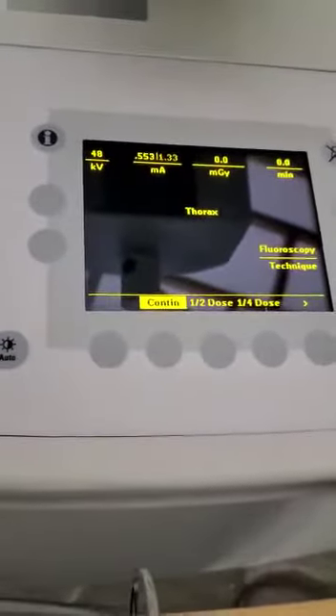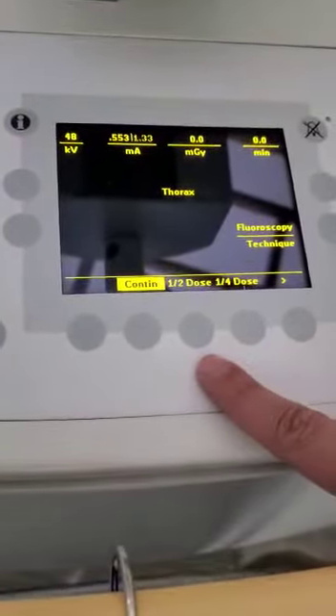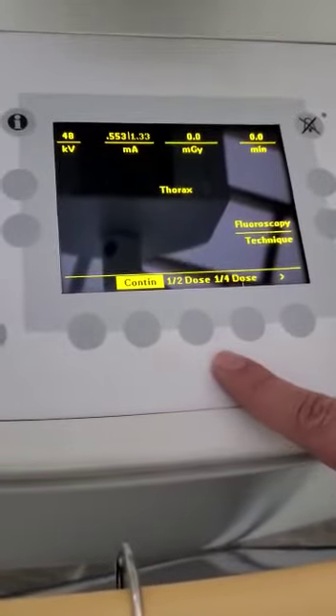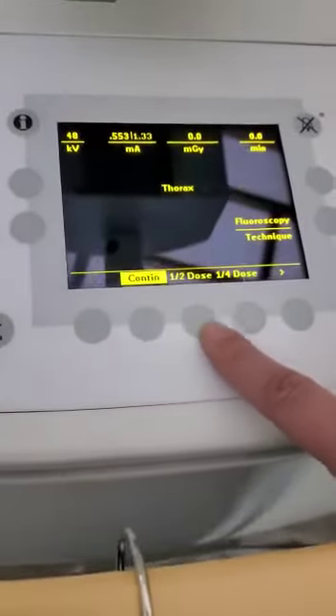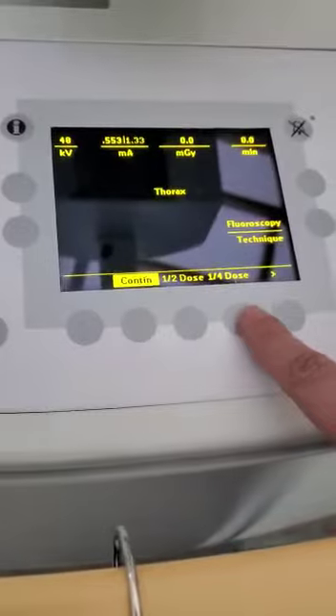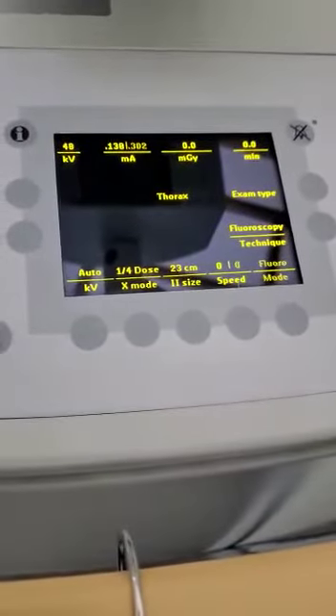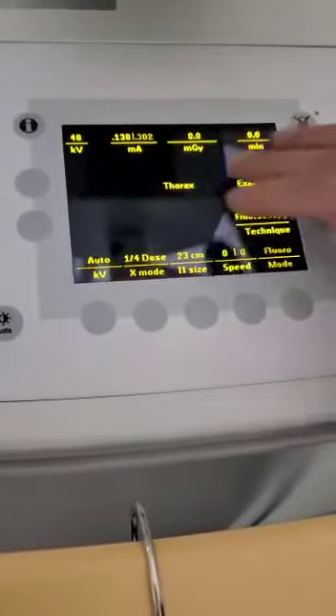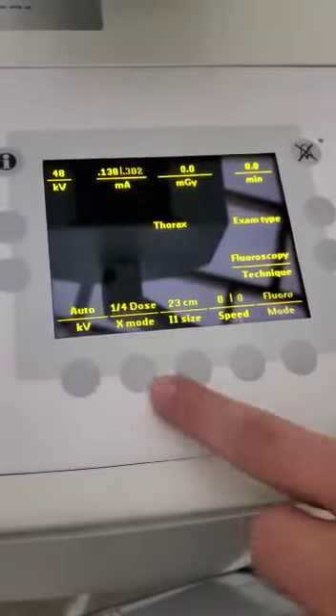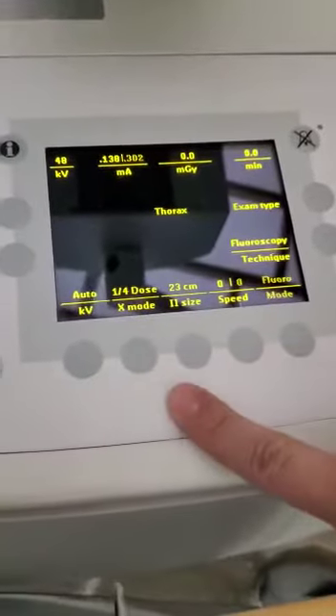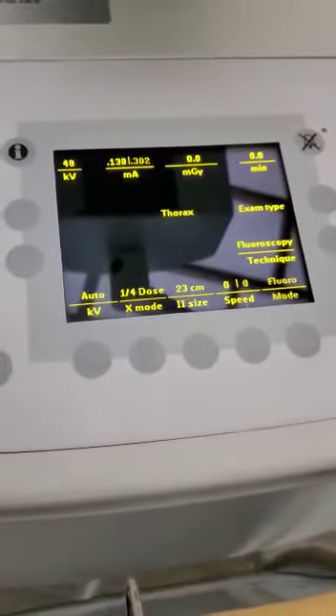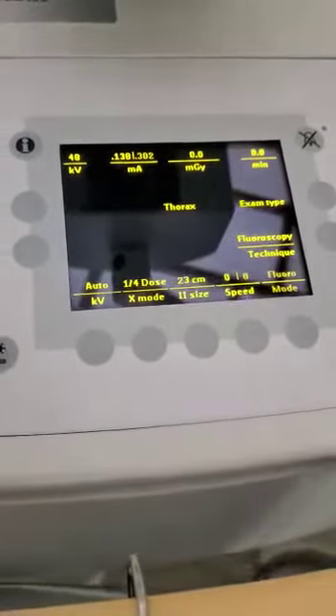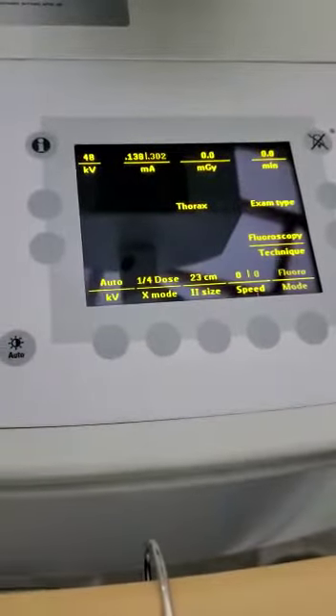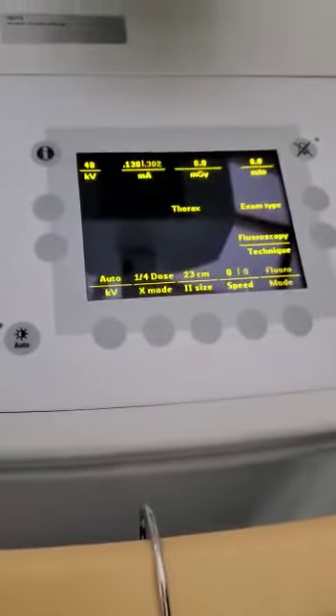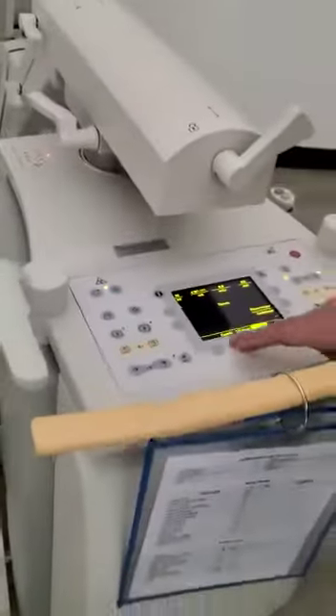You can go continuous, you can knock down your radiation on high definition, if you want, on the right foot switch. You can get it all the way down to a quarter dose if you want to. If you just want to select thorax, head, spine, HQ orthopedics, and operate it out of quarter dose for the rest of the day, you can hit that right foot switch or that right hand switch, and it's only going to release a quarter of the normal dose for that preset. That's your dosage. That's also your x-ray mode.